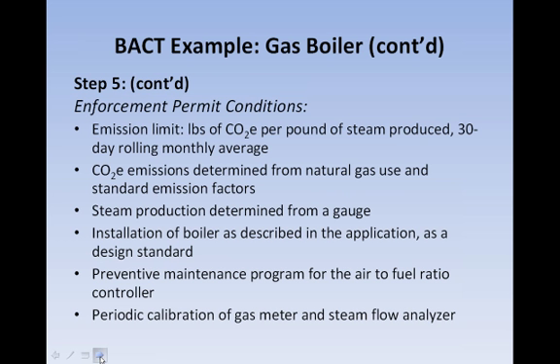In addition, there would be a requirement to install the boiler as described in the application as a design standard. Also, there would be a requirement to implement a preventive maintenance program for the air-to-fuel ratio controller on the boiler. And then finally, there would be a requirement for periodic calibration of the natural gas meter and the steam flow analyzer.